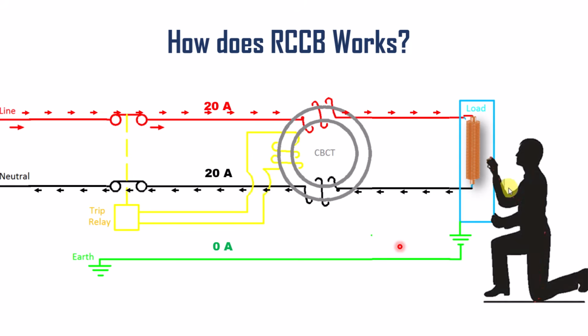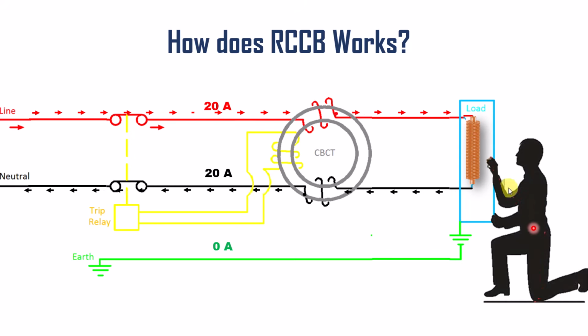There are mainly two sources of leakage current. First is the human, who accidentally comes in contact with the phase conductor. The current will start to flow through the body into the ground. The second source of the leakage current is bad insulation. Through the insulation, the current starts to flow into the body, which is directly connected to the ground. So there are two main sources of leakage currents.